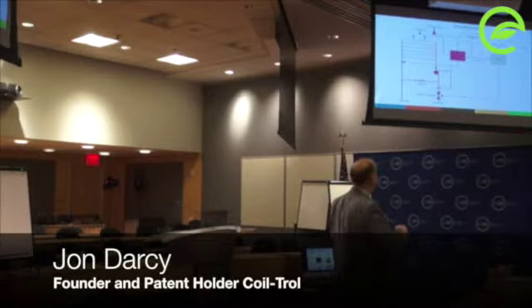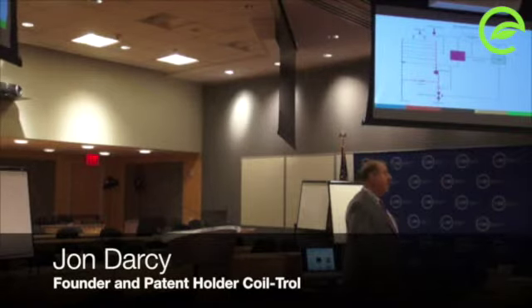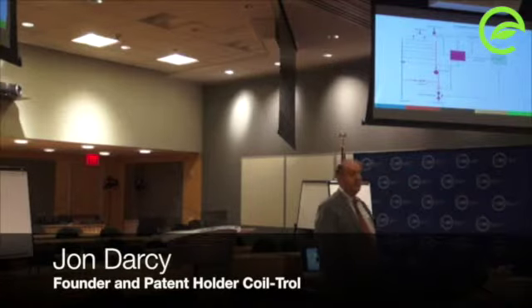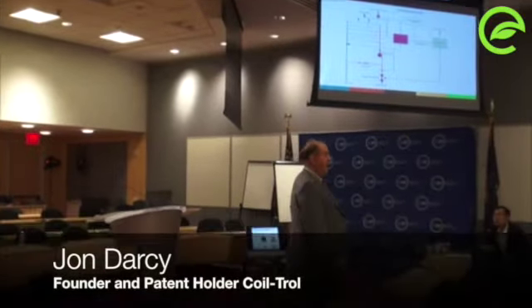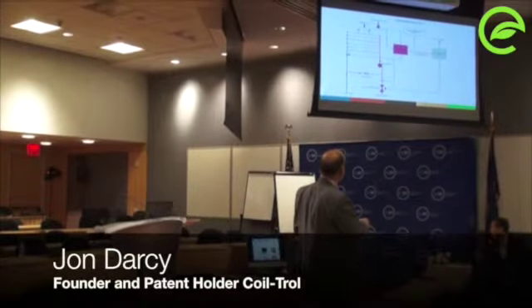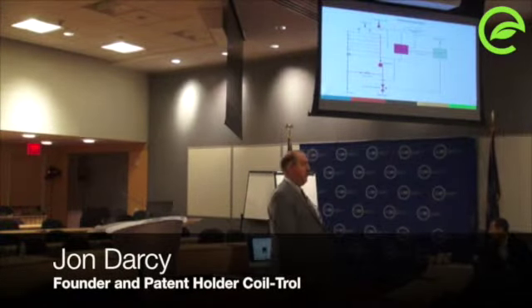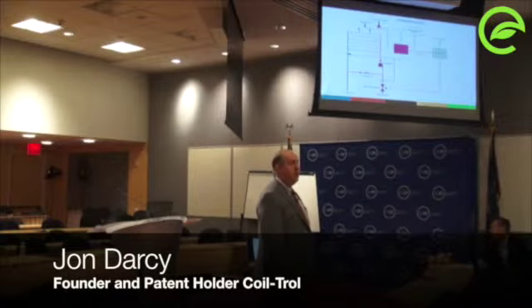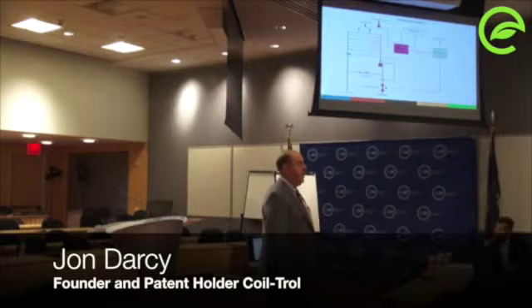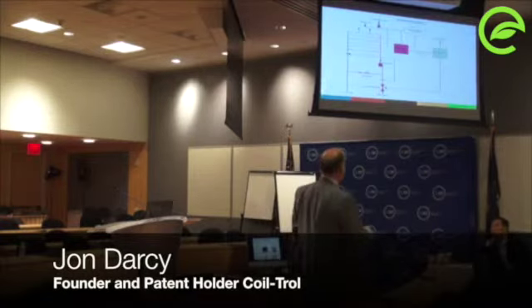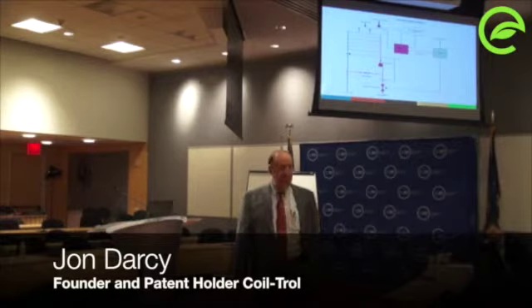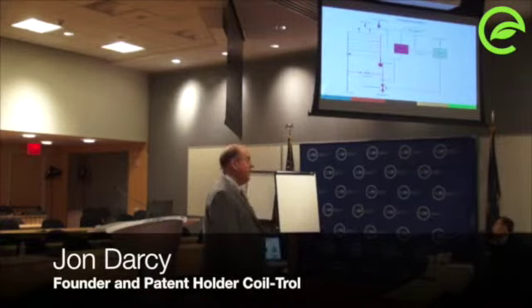That one pump, which let's say this is a 50,000 CFM air handler and it's a 2 horsepower pump, is around $1,200. Not a lot of money. And this pipe going across is probably a 2-inch piece of copper. So the installed cost of this thing is low, the payback is in months. Not years, in months. And it solves a lot of your balancing problems. You'll never need a balancer again.